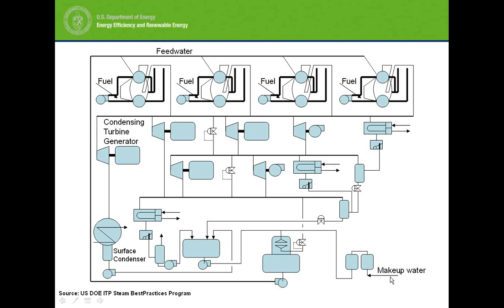And makeup water is basically what is required to complete the mass balance of the water steam side. Any condensate that is not recovered is to be made up by makeup water. Any other losses that happen on the steam side are made up by makeup water. All that ends up into a common tank. From there it's pumped into the deaerator, boiler feed water pump sends it and completes the loop.